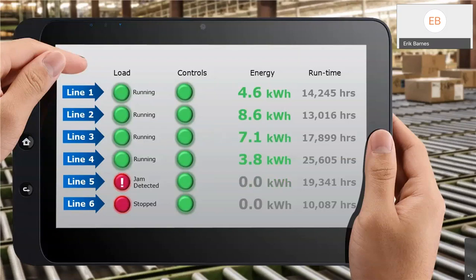Let's say things are running again. Okay, line 5, I've got a jam detected, right? So we can shut the line down. However you want to program it, maybe you want it to try to auto fix the issue, reversing it a couple of times. But either way, the operator knows I've got an issue on line 5. Let's stop running product down that line and use the other lines that are available. Or let's say maybe line 4, I've got an undercurrent alarm set up to let me know when I'm not using the line, right? So, hey, line 4 is running, but there's nothing on it. There's no load. So let's shift things that way, or let's turn it off, right?